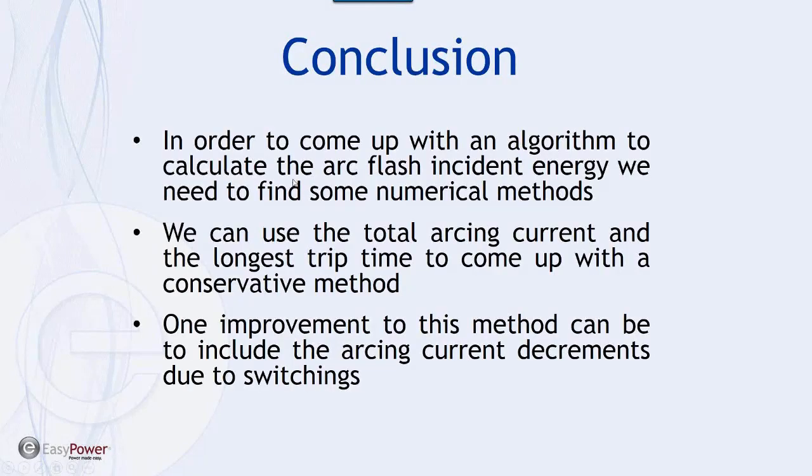Now, conclusion. In order to come up with an algorithm or approach or method to calculate arc flash incident energy, we need to find some numerical methods, and I gave some background in terms of how different software packages approach it. We can use the total arcing current and the longest trip time to come up with the conservative method. Again, this conservative method could be a controversial term, but I clarified what I mean by conservative method.